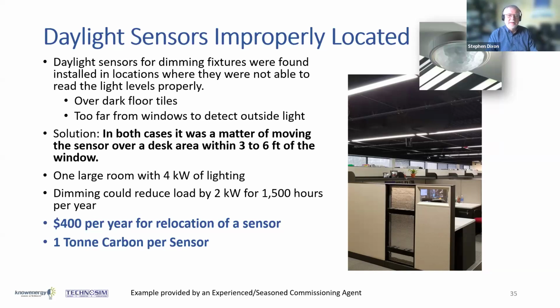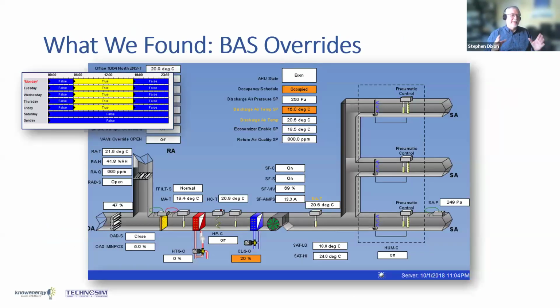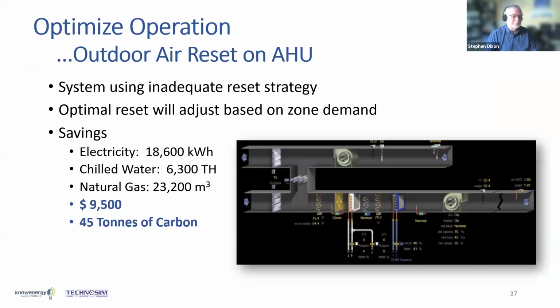So simple things, again, identified through a structured approach to waste reduction, recommissioning, or existing building commissioning. I can't say enough about these things. Every time I show a screen like this, a building automation screen, and I'm sure many of you have seen these, they ultimately find opportunities, and the big one is always things that are being overridden. Why are they being overridden? Beyond the overrides, if you were to spend enough time looking at the screen, you could probably find other opportunities too. As my friend Michelle says, the building automation system is probably the biggest liar in the room, but it may be the biggest opportunity too. It's supposed to save energy, but sometimes it's not. If we can get to those opportunities through it, that's certainly a good channel.